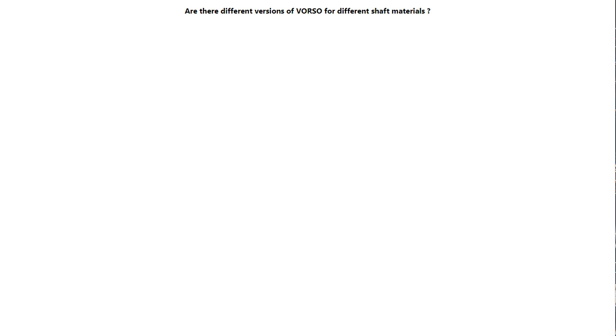Great question. So as we go to release, we're going to have two or three different, most common shaft materials out there, so you'll just need one version of the Vorso. However, if there are very specific shaft materials not listed on our data sheet or not part of our initial release, as one of those key components, it would be an update or a change really to the calibration in that interface module. Granted, that would most likely be a custom unit. We'd certainly have to evaluate that as they're out there. But again, we're going to be looking at probably three of the most common shaft materials that we see. But as we all know, as soon as we release those three, there's going to be several others that come in. We'll need to evaluate as we go. But again, just one Vorso for those three most common, and if it's outside of those parameters, it would be a custom.